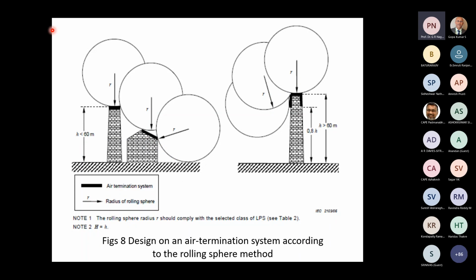So it's three rolled positions of the sphere, showing where it makes contact with these two tall buildings. So here I have to have either rods at the corners to see that the rolling sphere does not contact the surface, or rods plus mesh if required. That means if the area is very broad, mesh also. Here again, you'll see that this sloping area of this building needs no protection at all, whereas this area positively needs protection. Inside, of course, you don't have to worry.